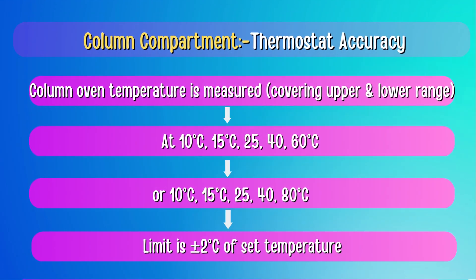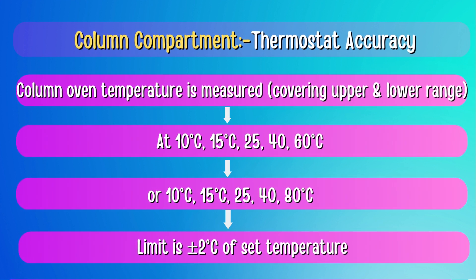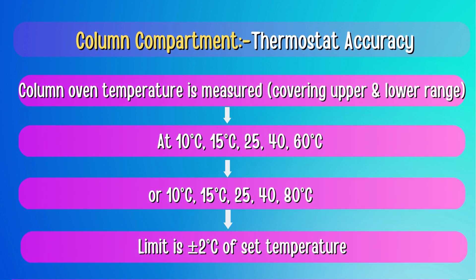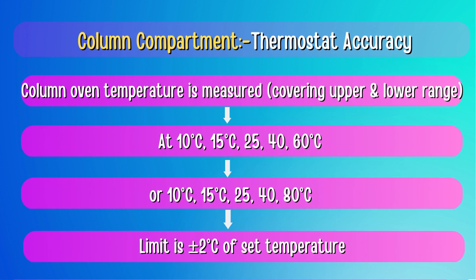For the Column Compartment, Thermostat Accuracy is performed by measuring column compartment temperature at 10°C, 15°C, 25°C, 40°C, 60°C, and up to 80°C, depending upon the make of HPLC being used. The limit is ±2°C of the set temperature.